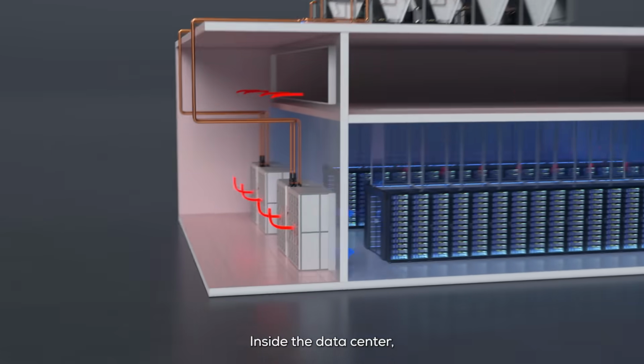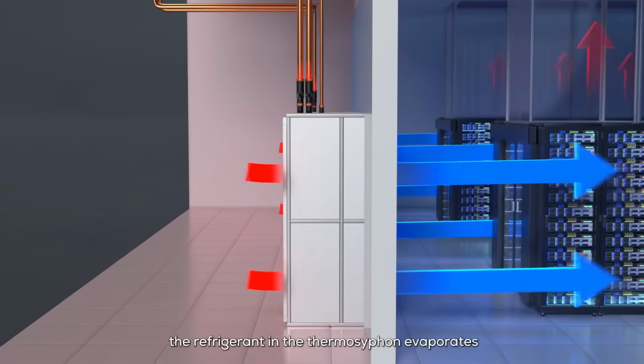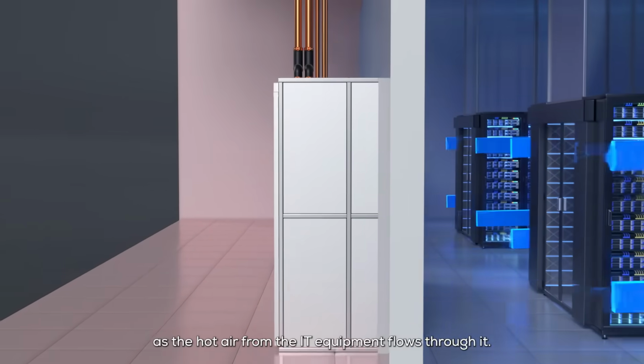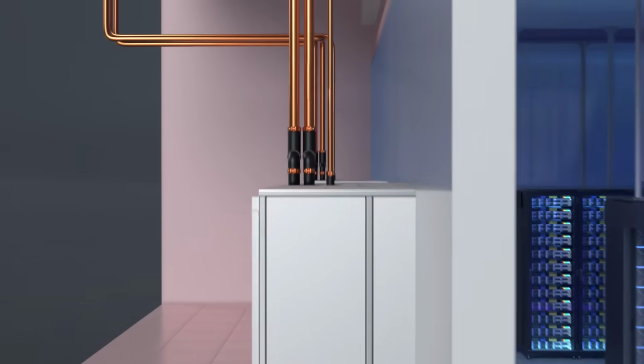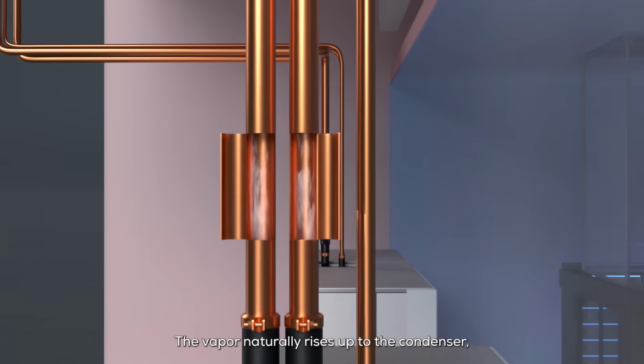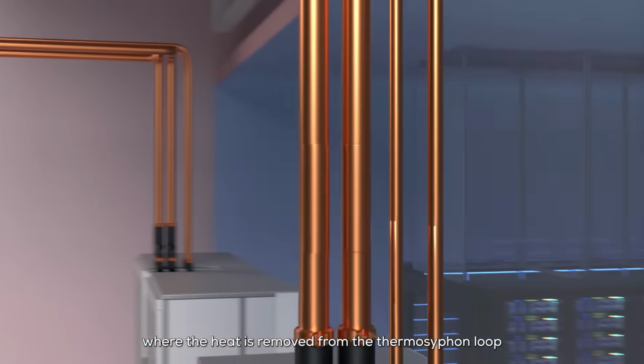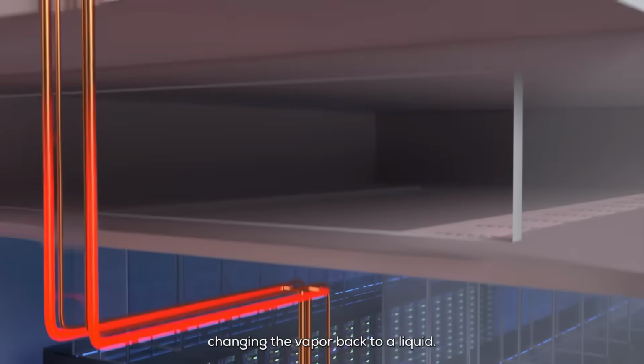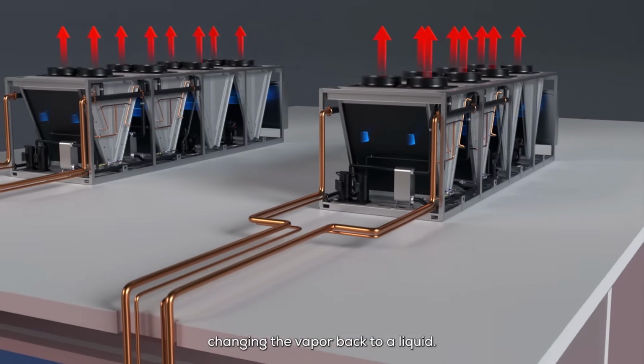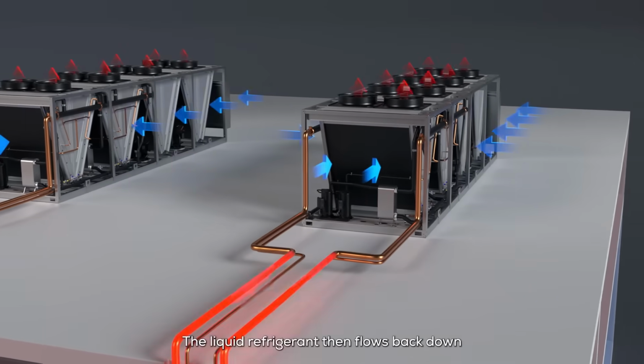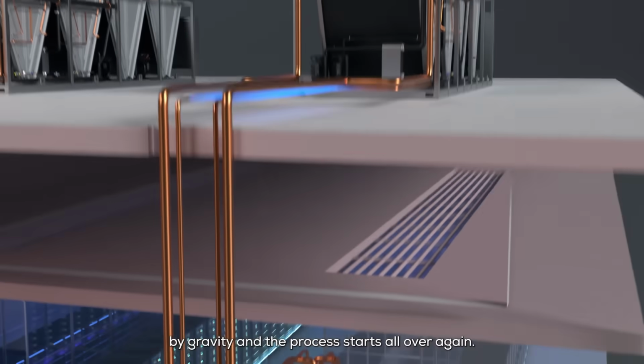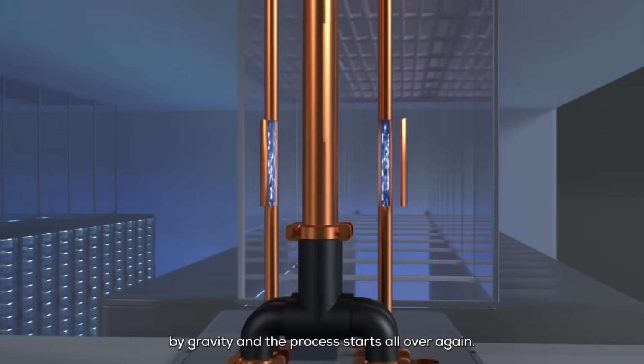Inside the data center, the refrigerant in the thermosiphon evaporates as the hot air from the IT equipment flows through it. The vapor naturally rises up to the condenser, where the heat is removed from the thermosiphon loop, changing the vapor back to a liquid. The liquid refrigerant then flows back down by gravity, and the process starts all over again.